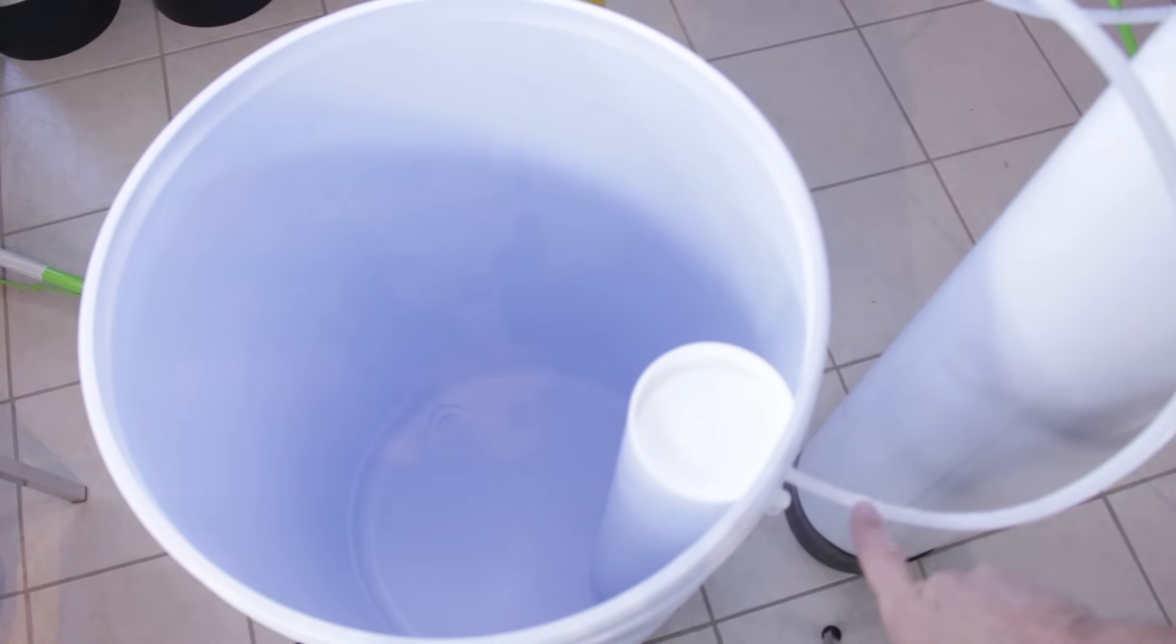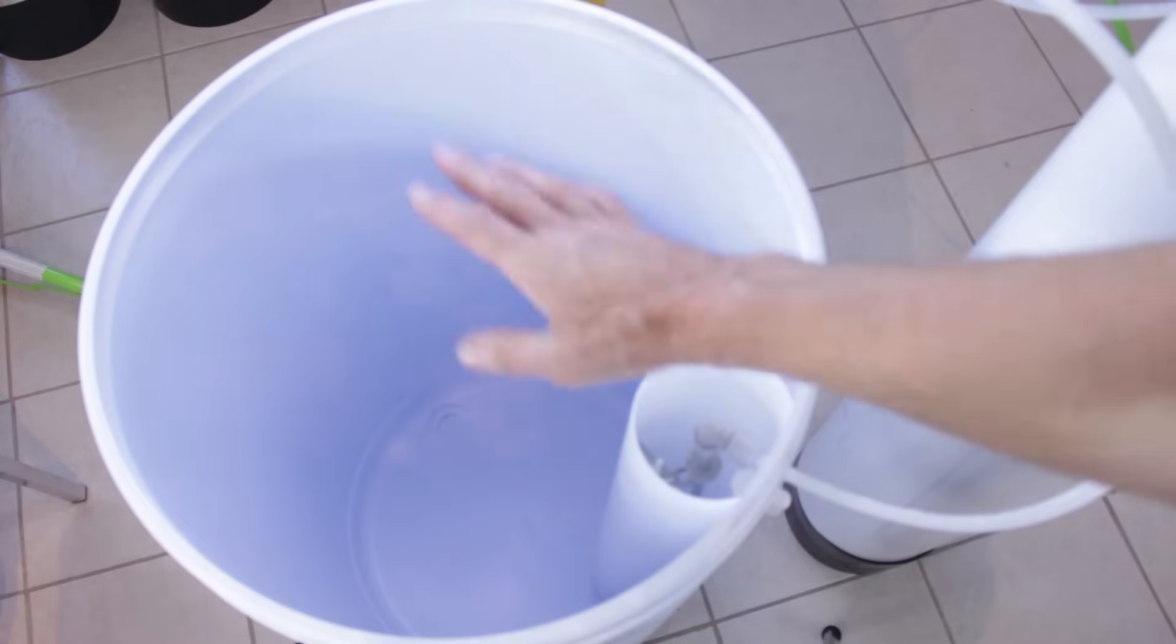The first thing you want to check is to make sure that this brine line is attached inside the brine line level control or the float. You can see the float is right here and this line here needs to be attached properly to that float. If it's not, the water just flows in and keeps going higher and higher. That's the first step to check.